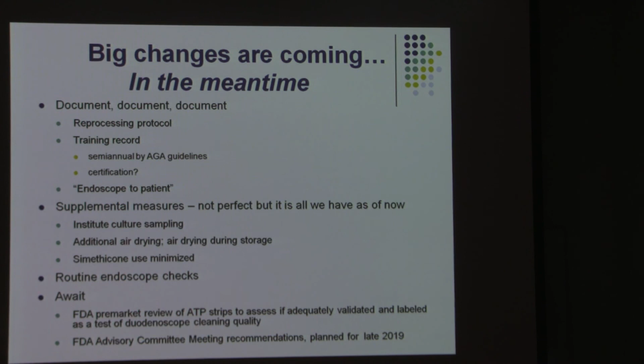Clearly, the FDA recommends that we institute culture sampling. Additionally, air drying during storage could be considered. Simethicone use should be minimized. Routine endoscope checks should be instituted, and we await FDA pre-market review of ATP strips to assess if they are adequately validated and labeled as a test of duodenoscope cleaning quality, and FDA advisory committee meeting recommendations that are planned for late 2019. Thank you so much.